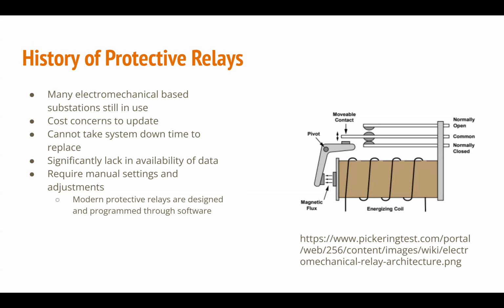One of the biggest difficulties with electromechanical relays is we don't have good availability of data from these. I wouldn't even call these IEDs - I'd call them electromagnetic relays because they don't have real intelligence built into them. They generally won't have the ability to plug in a serial cable and get the data out. So we don't have visibility into the amount of current it's currently sensing or what the voltage is. If one of these relays trips, we know something went wrong, but we don't necessarily have the data to look into why it tripped and what we can do to stop that from happening in the future - was it just a nuisance trip, something programmed wrong, or did we actually get too much current on the line?